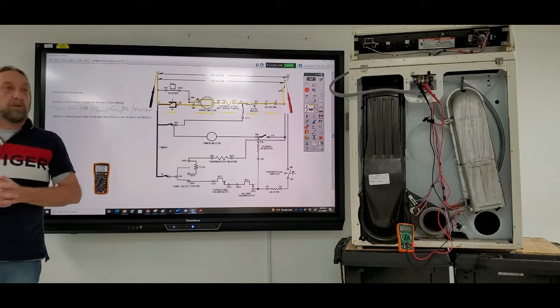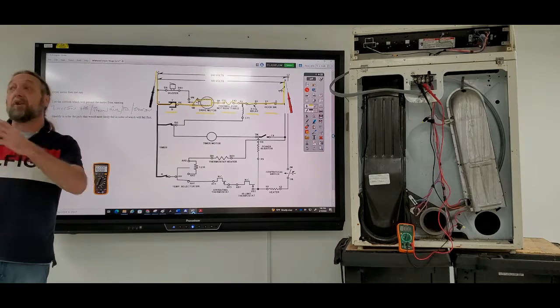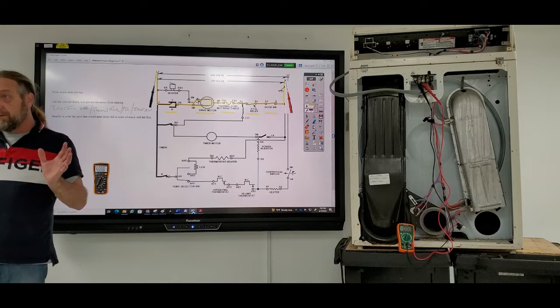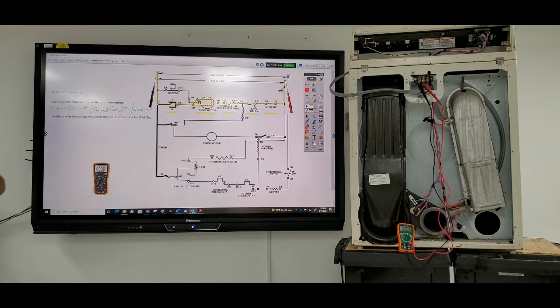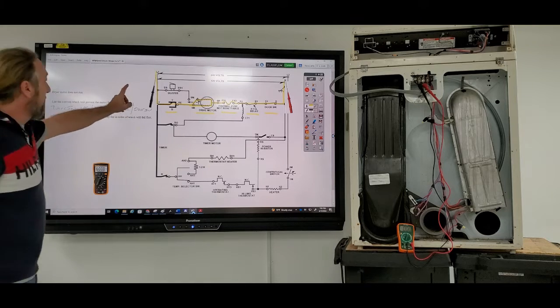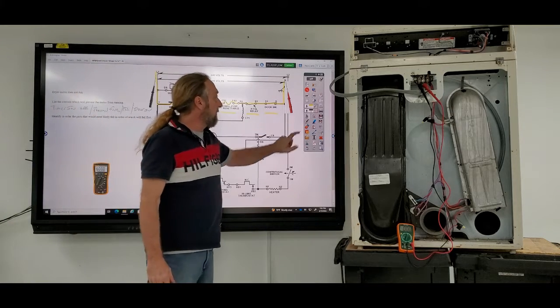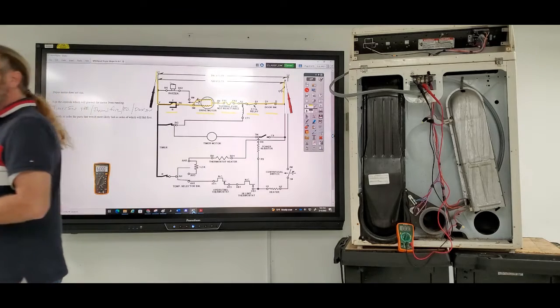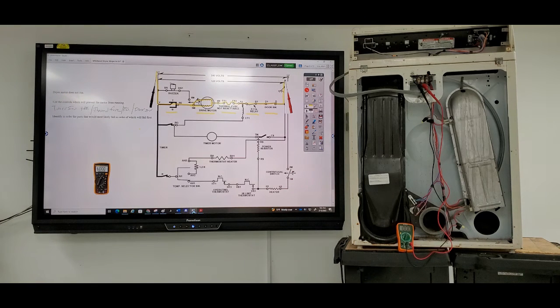But we're going to assume that we press start and the motor doesn't even hum. It doesn't do anything. Okay? Now the proper test would be to go to where? If I have voltage at the machine, what should the next step be? The door switch? Check the door switch. Anybody got any other ideas?